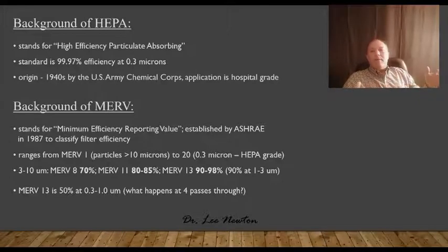Don't take this information that I'm giving you and say, gee, I need to upgrade my filter from whatever it is to a MERV 13. The reason for that is the denser the filter material and the more tightly it's woven and the more it filters out, the more it impedes the flow of air through it. So you could upgrade your filter without the right knowledge, and you could create a constriction in airflow, so then you won't get the conditioned air as much in terms of cubic feet per minute out in your diffusers. You could also burn out your blower motor, and I don't want that to happen because of information I gave you.